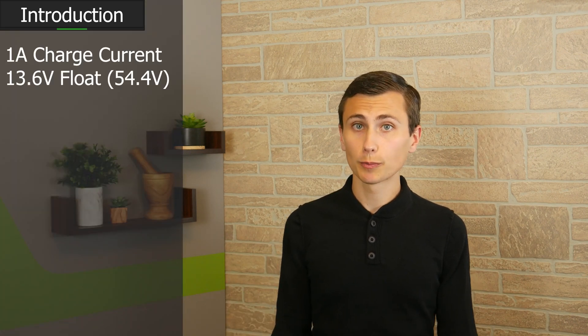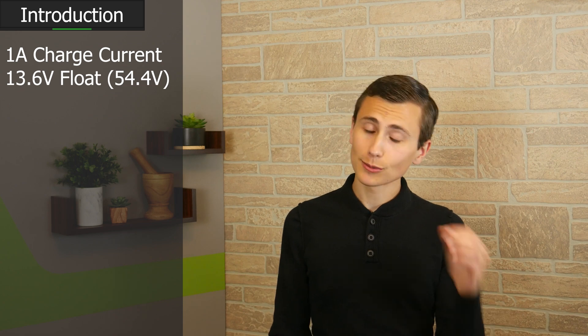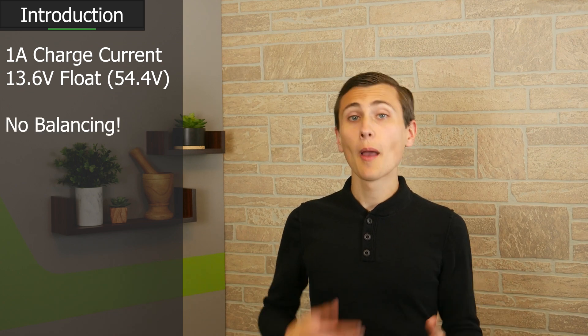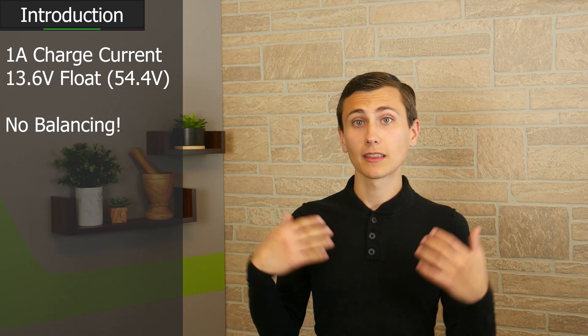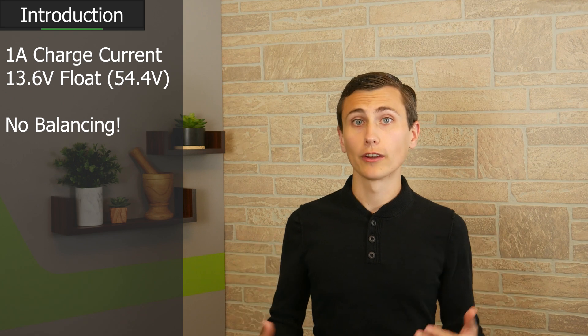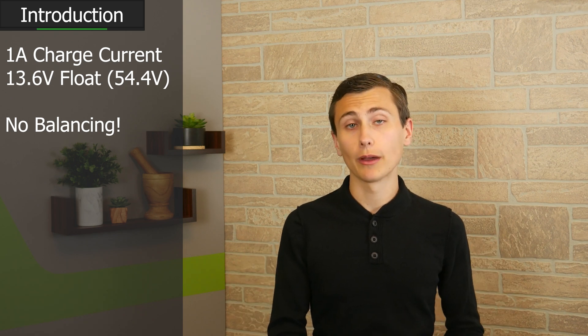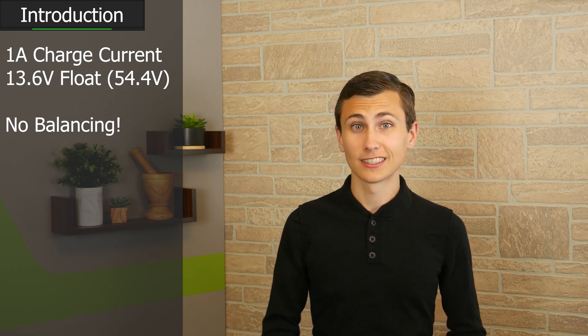The top level requirements are this: up to 1 amp charging current, a float charge voltage of 13.6 volts per battery. The supply isn't responsible for balancing the batteries, but it is responsible for providing the power required to charge them in a reasonable amount of time. Let's dive in.